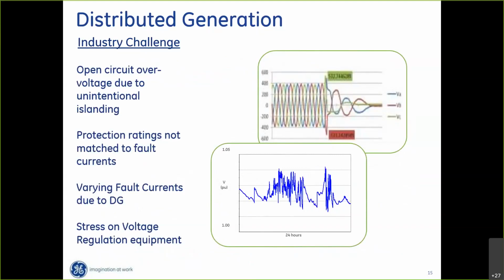One is open circuit over voltage, unintentional islanding. Two would be protection ratings that may not match fault currents. When we set the relays, we did a short circuit study, but we only looked at the source side contribution to the fault. Now as the penetration of distributed generation grows, we have a load side contribution. So our protection rating may not have taken that into account, right?